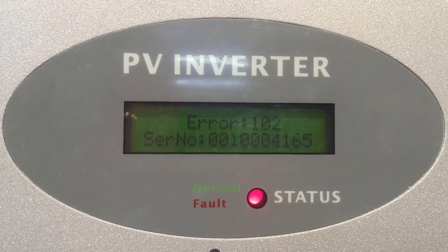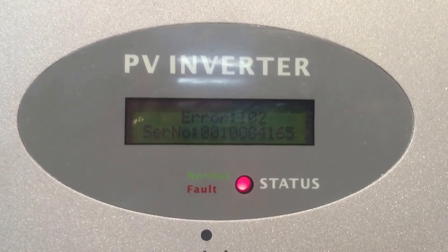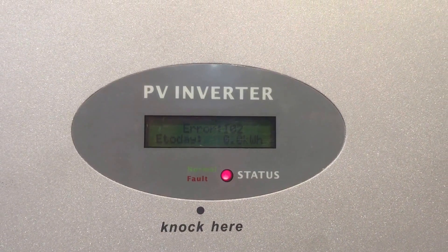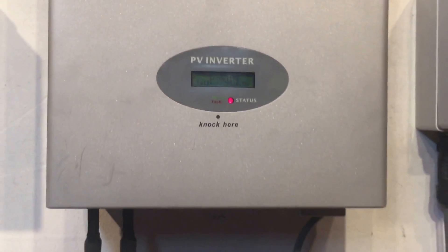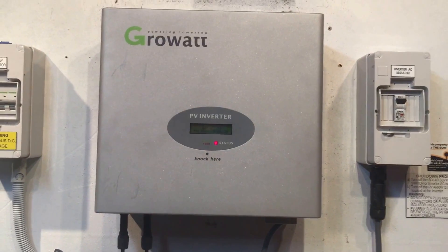Error 102 means that the inverter has a consistent internal fault. With any problem with a solar inverter, I always recommend trying to reboot the system. It can be like a computer — it can get a glitch and if you reboot it, it might start up again. I'm not all that hopeful here, but we'll give it a go.